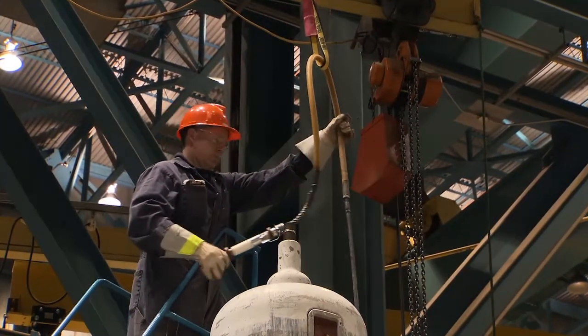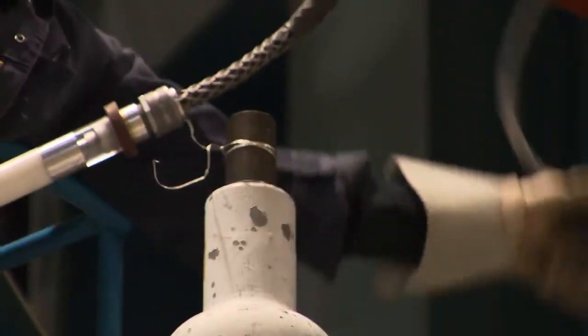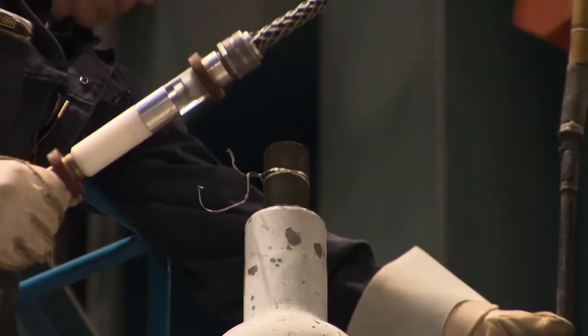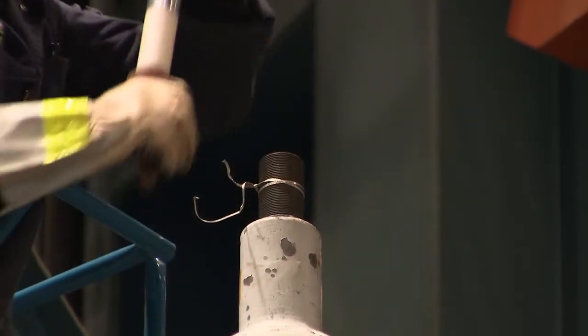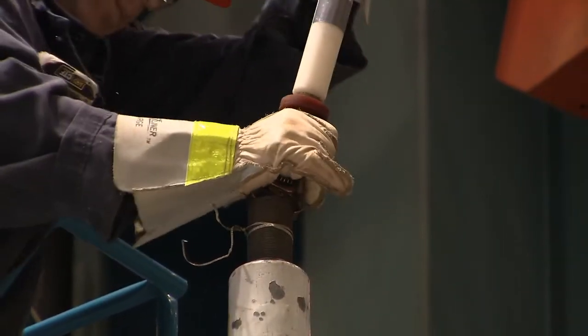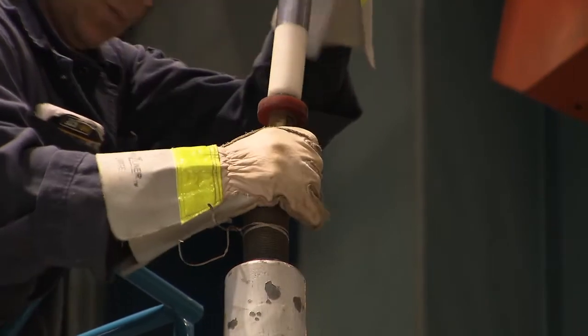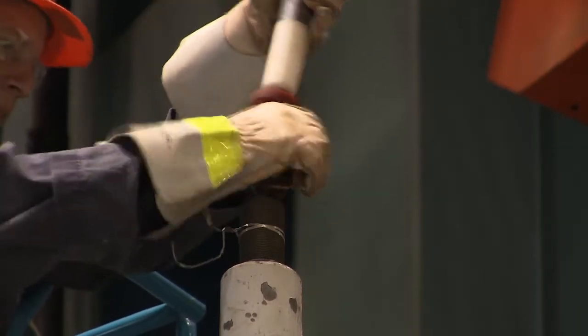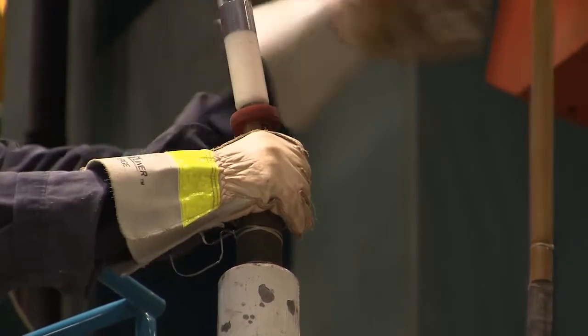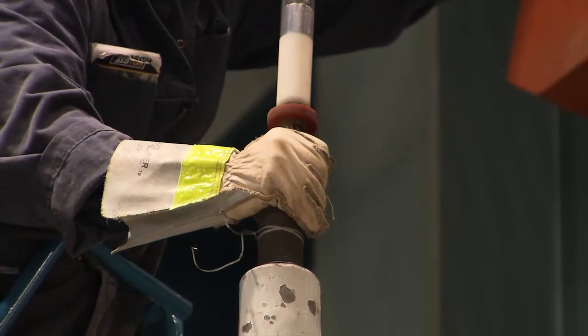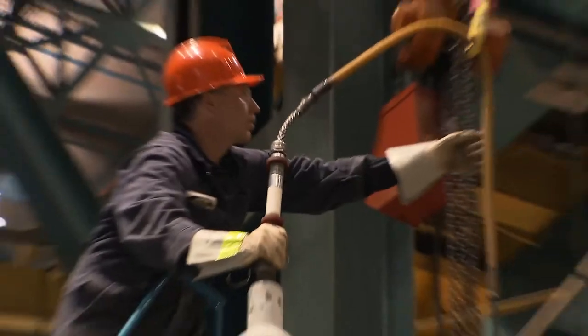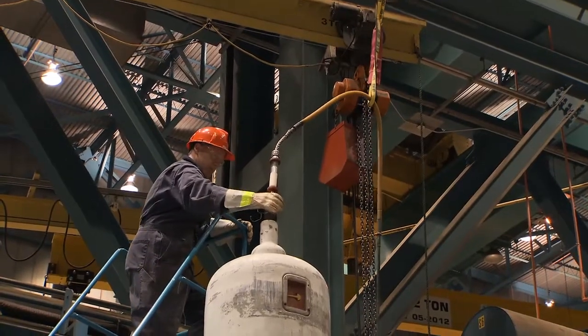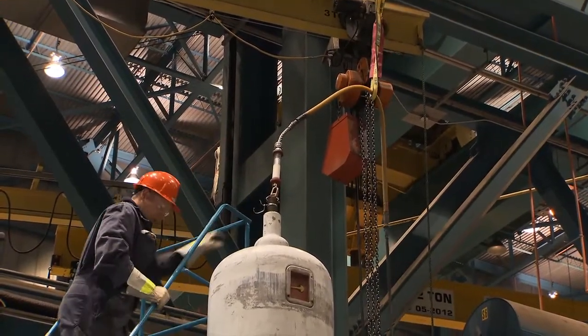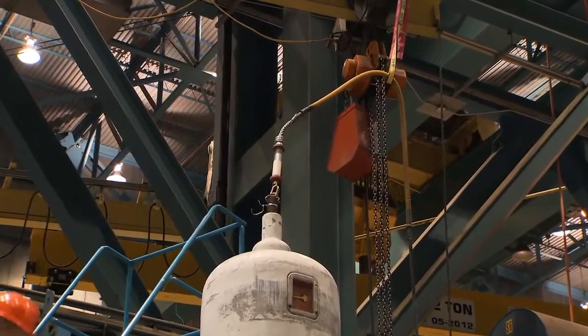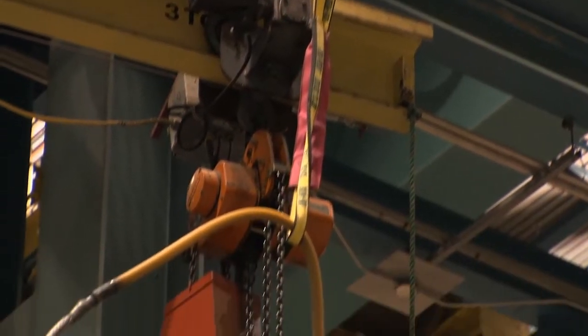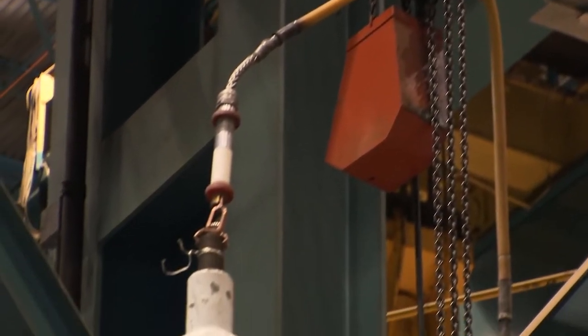Attach the thicker orange high voltage lead cable carrying the current directly to the top of the conductor rather than the copper strand. Support the weight of the cable on a sling suspended from the hoist hook. Ensure that it is safely in position above the terminal on the bushing.